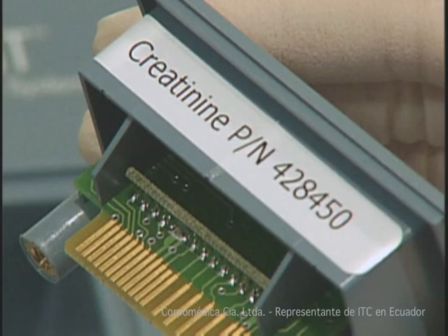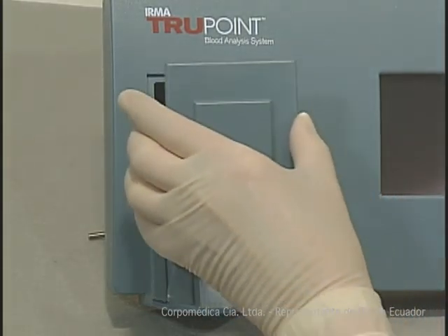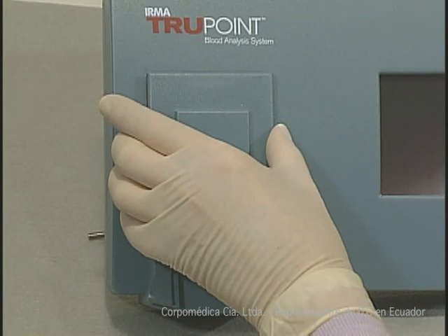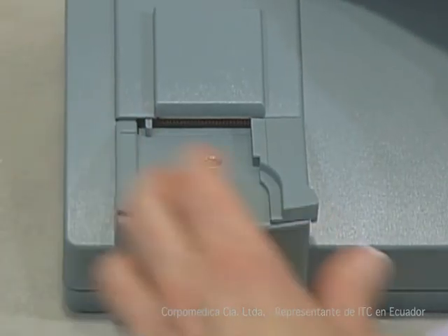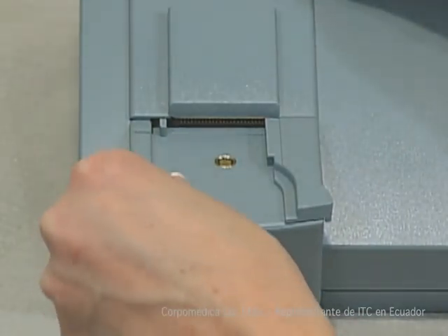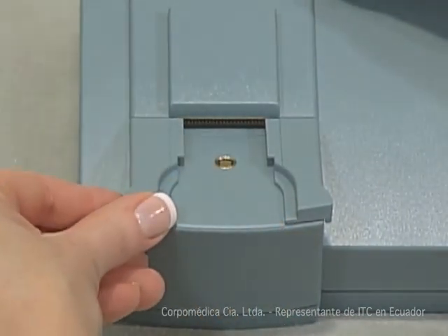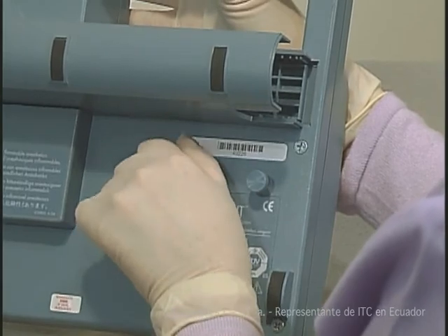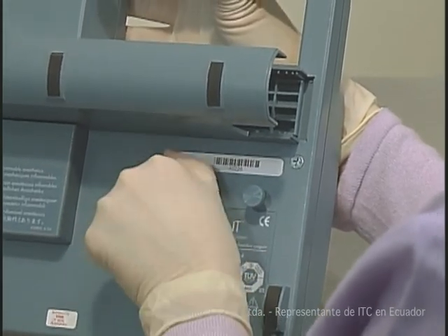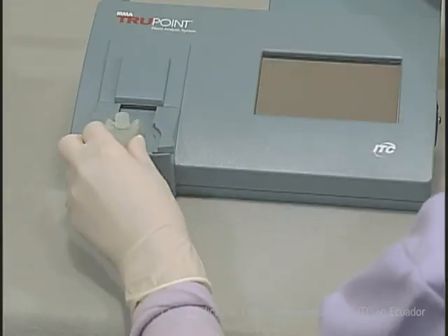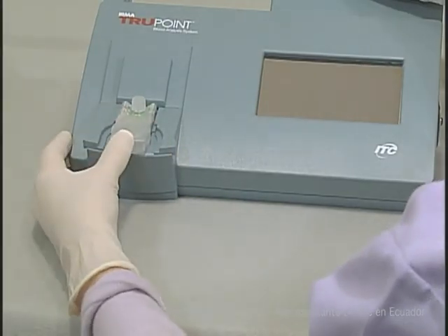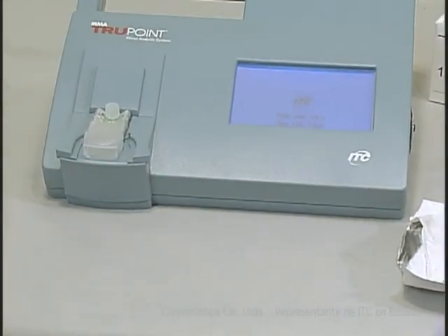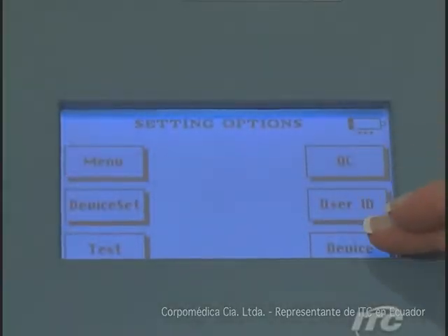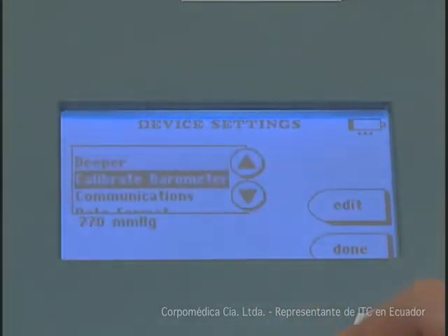Make sure that the analyzer's connector is dry and that no foreign materials are present before installing the new edge connector. If the edge connector has a label with the word creatinine and a part number on it, the replacement edge connector must have the same label on it. Place the new edge connector into the analyzer and push down on the assembly until the cover is flush with the instrument top. Reinsert the left and right guides until they snap into the edge connector assembly. Reinstall the two thumb screws from the bottom of the analyzer while holding the cover in place. After installation, verify that a cartridge can be inserted. Then run electronic quality control. On an annual basis, verify and, if necessary, calibrate the TruPoint barometer against the barometer used in the clinical lab.